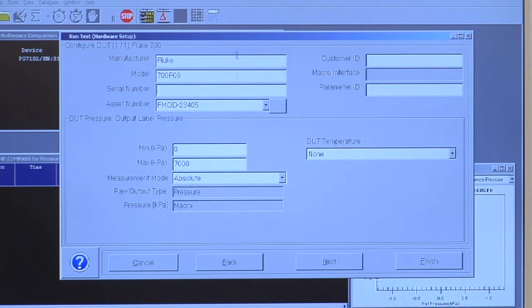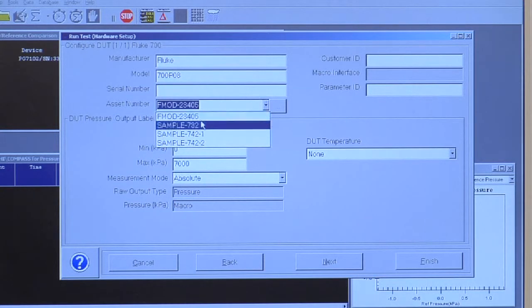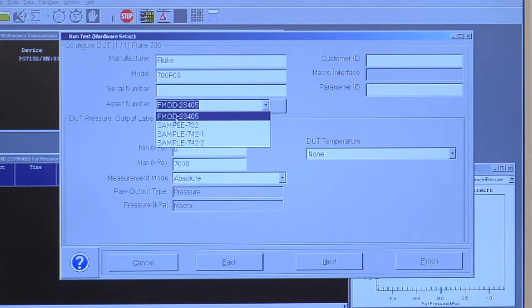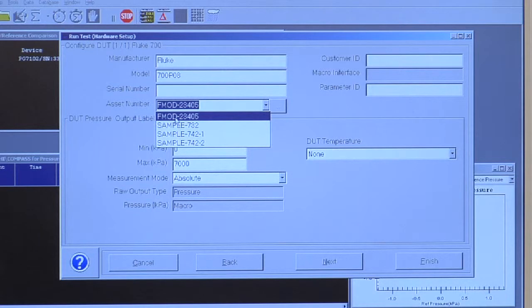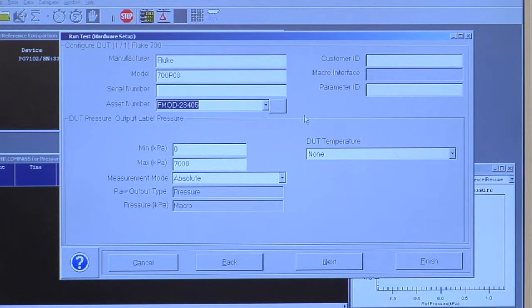Here's the pressure module. Note this is the METTRAC asset number. This was extracted from METTRAC. Within the tools options menu in Compass, there's literally a METTRAC tab that allows you to enable or disable METTRAC access while the test is running. That option is obviously on. Compass read the METTRAC database and loaded the specific asset number for this instrument.